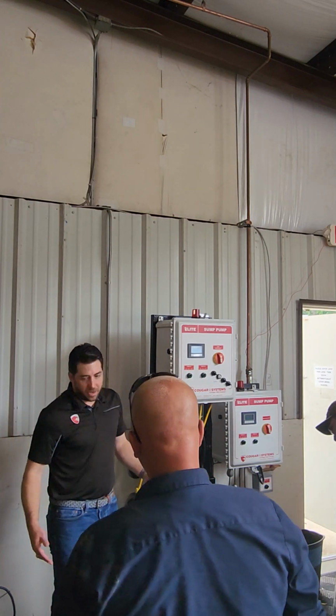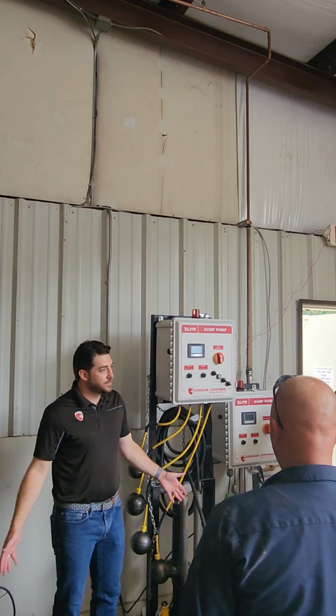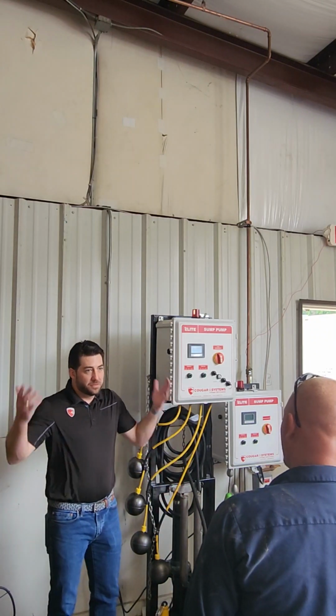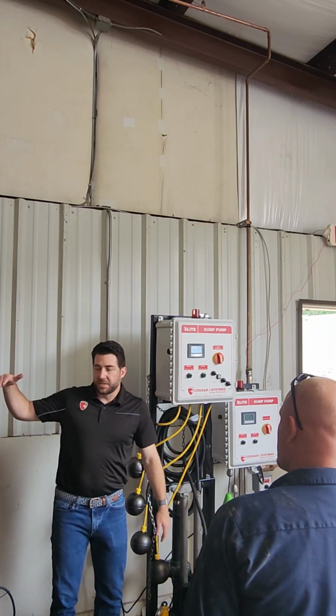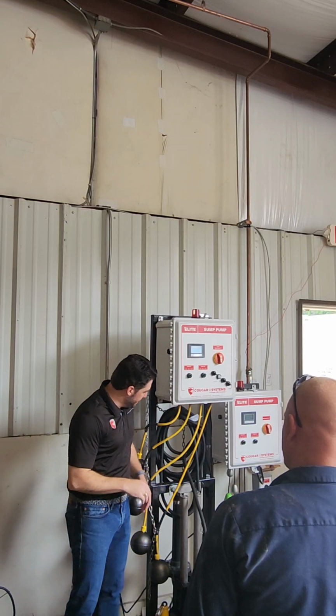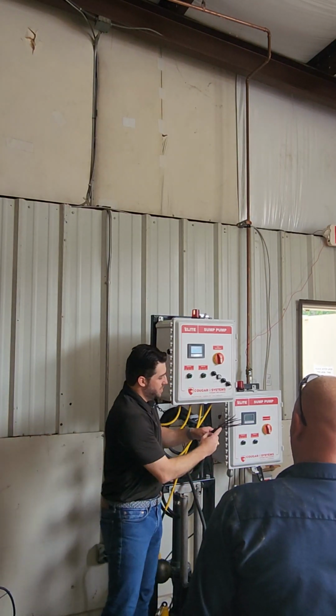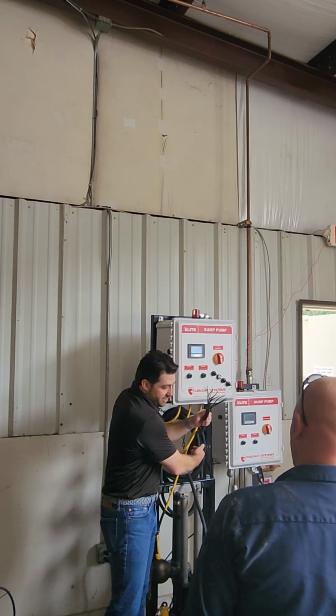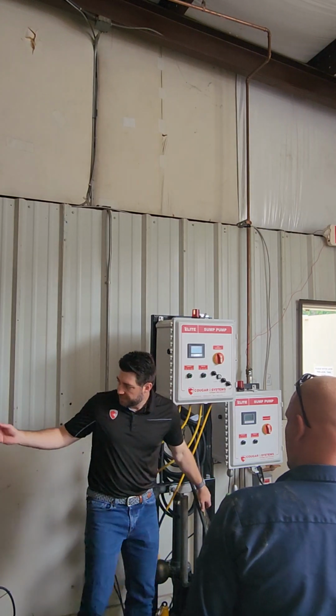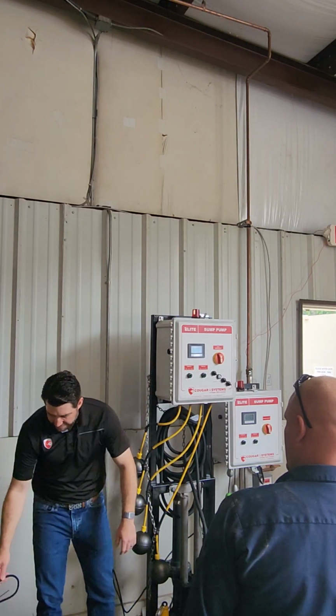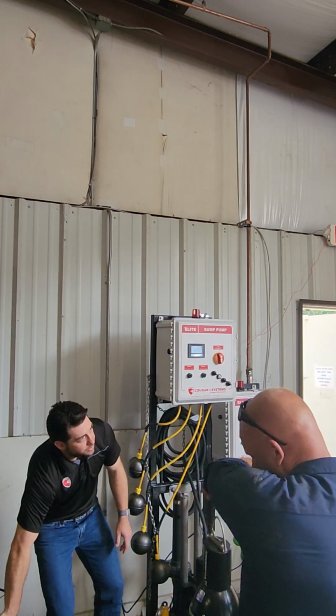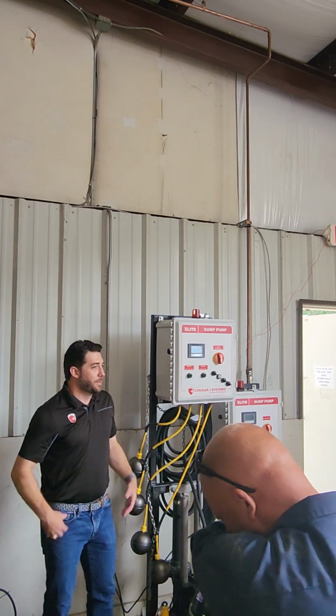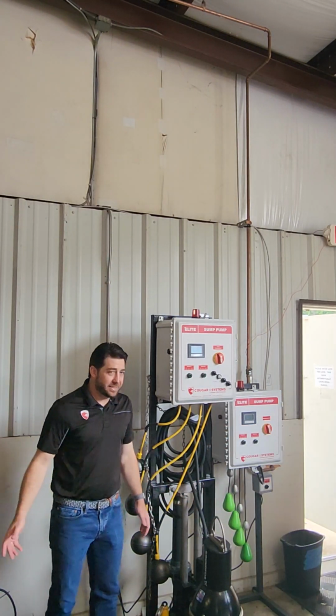Obviously these are designed to be underwater, right? But if the whole room floods and you get water into the panel, you get water into the end of the SO cable here, and it will wick down eventually and get down into the motor. So on this one, if water were to get inside this cable, it would go all the way down into the motor and ruin the motor. Bless you. But it takes some time.